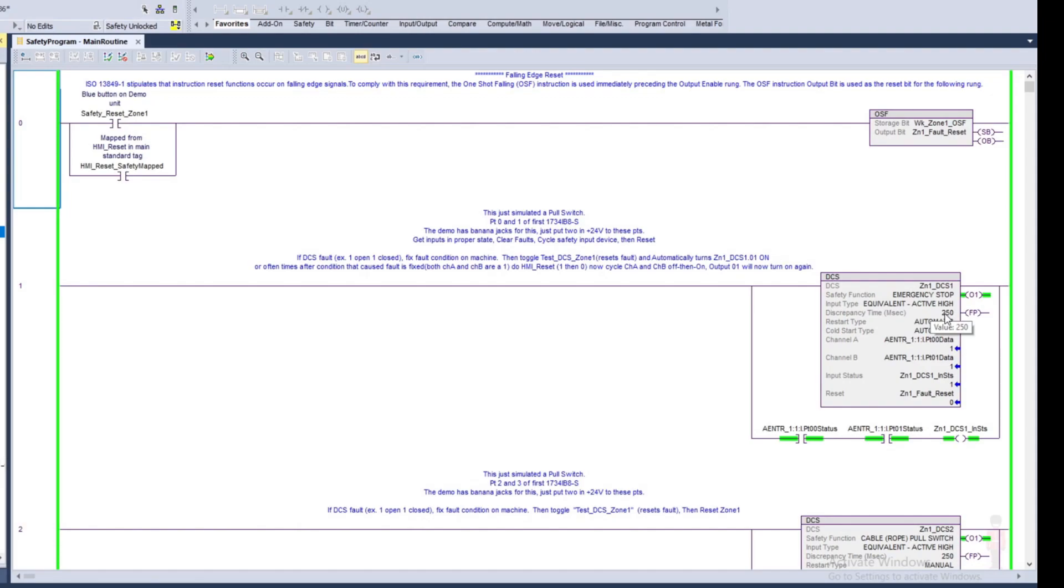If they don't then it's going to cause a fault because maybe a wire fell off or there's something defective with the switch. The restart type I've just got it set to automatic. You can set it to manual if you would like. If you set it to manual, then every time you hit the e-stop and you pull the e-stop back out, you're going to have to hit a manual start again or a reset.